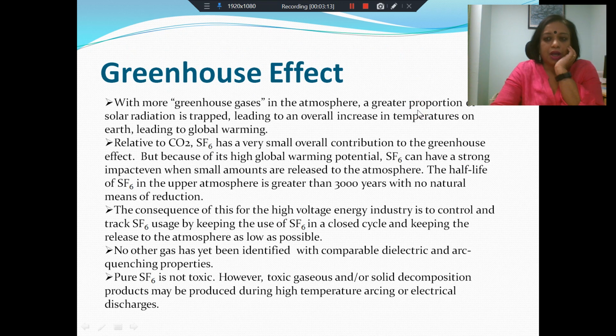The other concern that we have with GIS, which we do not have in air insulated substations, is that of greenhouse warming. SF6 is a greenhouse gas. Greenhouse gases, when they exist in the upper portion of the atmosphere, tend to reflect the rays of the sun. The sun's rays enter the atmosphere, and from the earth they're reflected back. And when you have a lot of greenhouse gases, they tend to send the sun's rays back into the earth, and as a result there is an overall increase in global temperature. So we have what is called global warming. Greenhouse gases contribute to global warming.